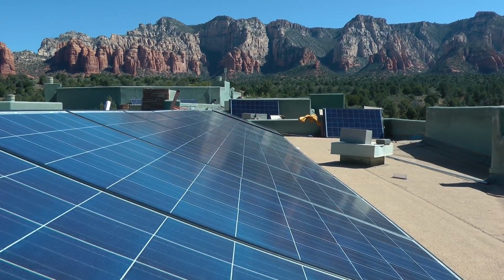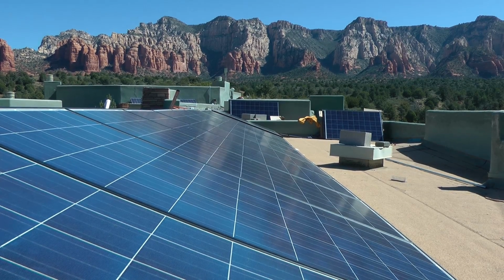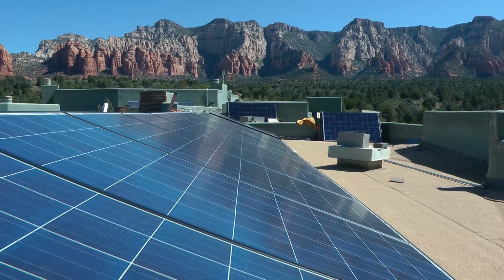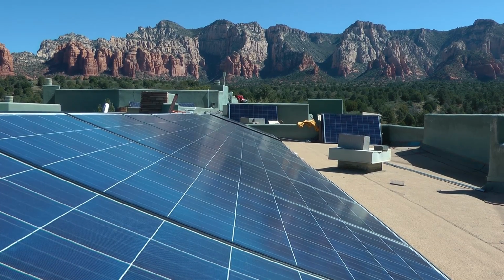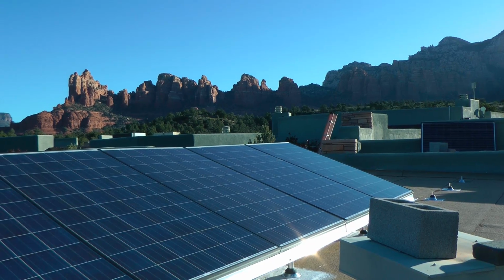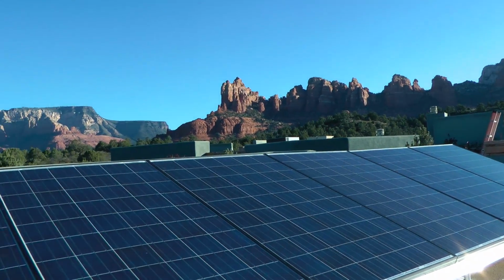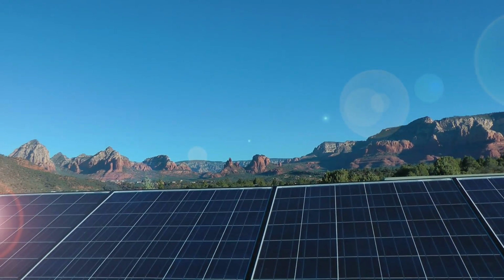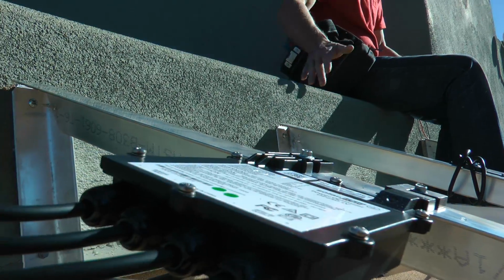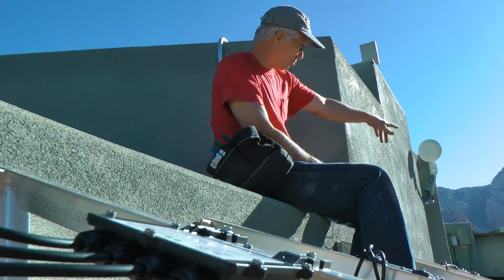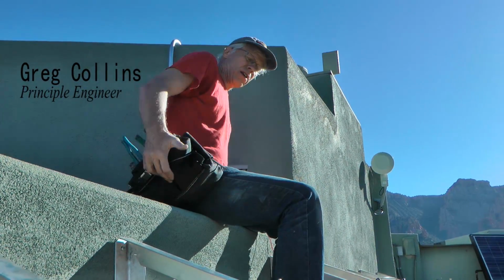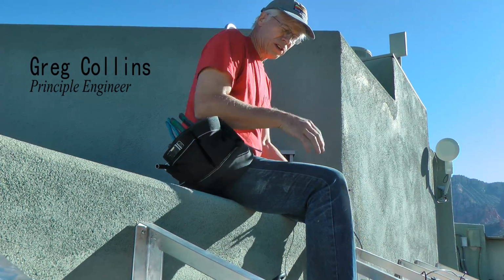This is a SolarEdge system. It's a distributed system where they have these modules distributed around the system, one for each solar panel. Each one of these manages its own solar panel, and it has the great benefit that each panel is individually optimized that way. If shade goes over and covers a panel down there, it doesn't affect this one.